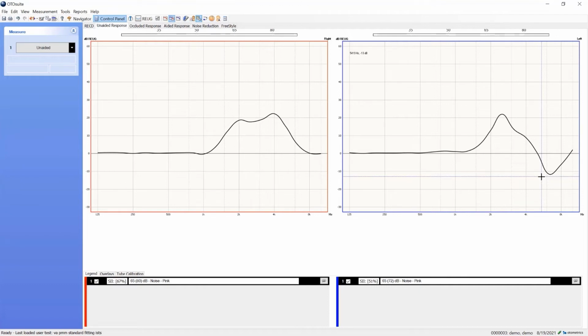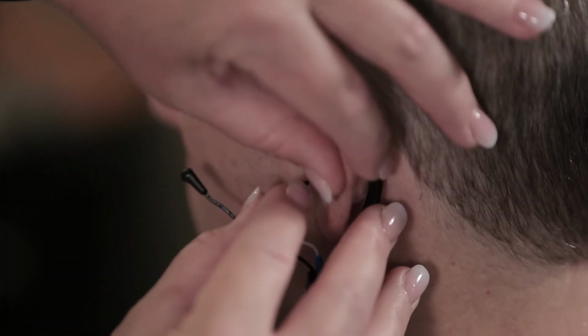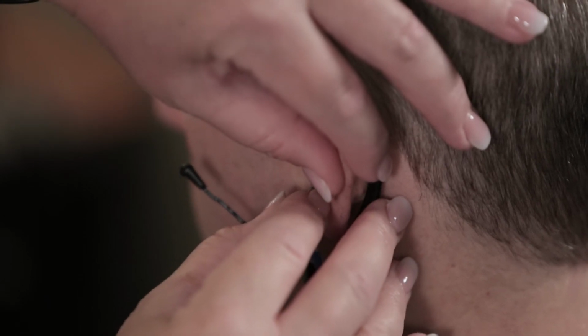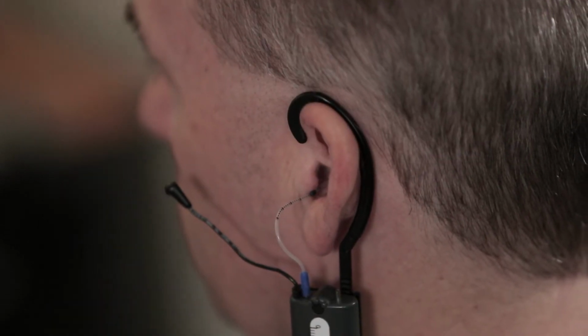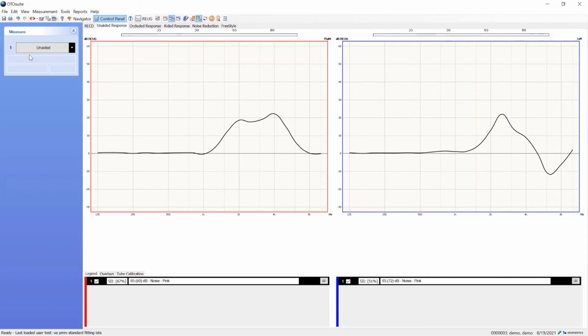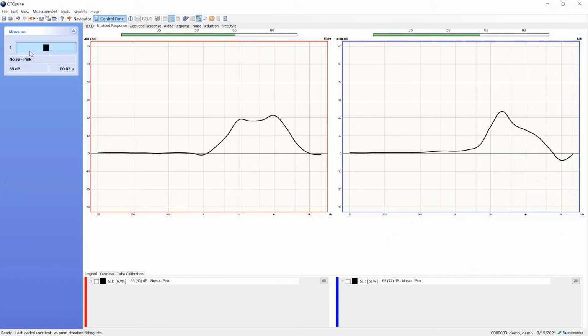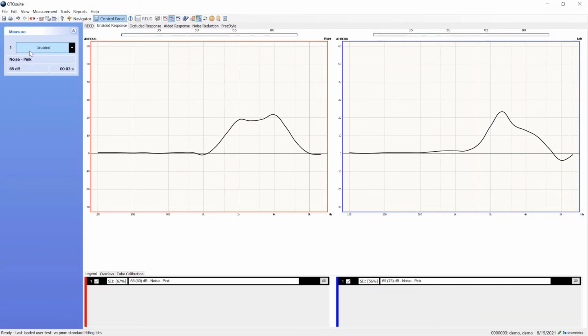The curve should not show a negative trough or fall below the zero line around 6,000 Hz in the REUG view. If it does, as you can see in this example for the left ear, you must reposition the probe tube deeper into the ear canal and repeat the measurement. After repositioning the probe tube, the REUG curves show proper probe tube placement for both ears.